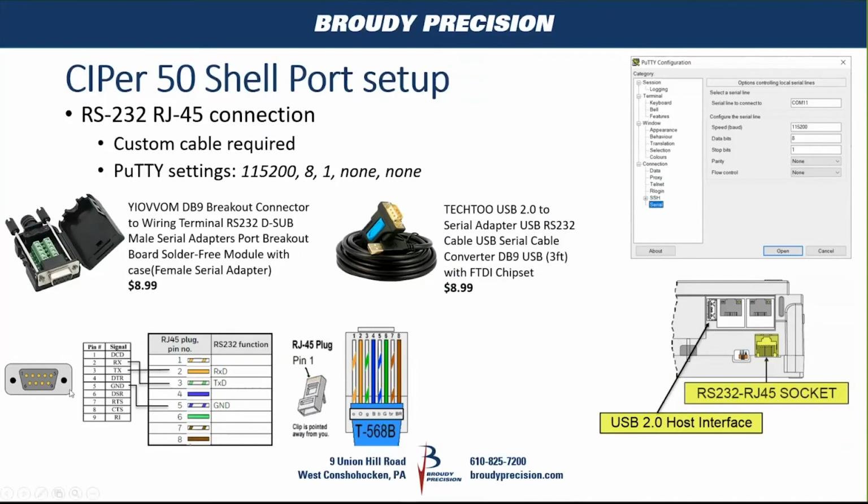Basically it's a 9-pin adapter, but it's only using 3 wires off of an RJ45. So it's using pin 2, 3, and 5. I looked at my old RJ45 cabling that I used for the old 403s, and it is different. I believe on the 403s it was using pin 6 instead of 5. There was a wiring difference and it wouldn't work.